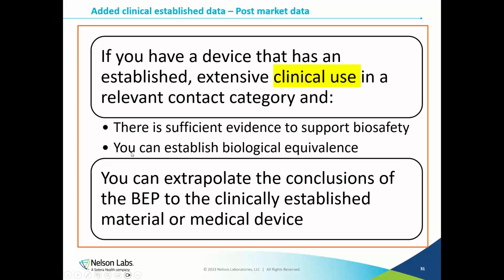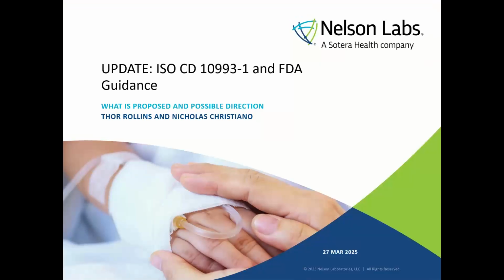Yeah, and I would agree with Thor on that. Conceptually, my mind goes to the same thought process we have with implantation studies. Sometimes there's a business decision that we want to submit the 510(k) and get it under review. Perhaps we have results from a short-term implant study, where a 13-week or 26-week study is actually underway. So we show the reviewer and the regulatory body the data we have currently, that we are considering further data, but that we are mitigating those risks, and we believe the residual risk is acceptable for pushing this product out and seeking compliance.